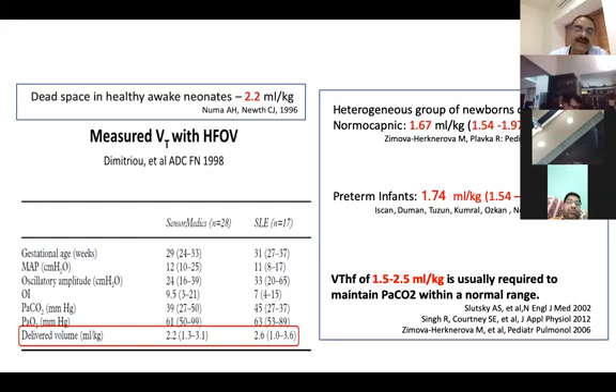And somebody had tried to measure, in 1998, Dimitri et al. tried to measure the delivered tidal volume when babies were reasonably stable on high frequency. In Sensormedics, they found it was somewhere around 2.2 ml per kg. In SLE, they found slightly higher. I told you it's a less powerful machine as compared to Sensormedics, so 2.6. But this was before the concept of gentle ventilation. So gentle ventilation has come in conventional ventilation, and now we have it in high frequency as well. So these values probably may be on the higher side.